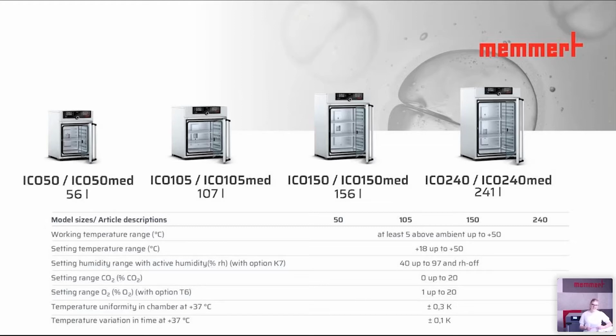With our special Memmert heating system, we were able to perfect our temperature uniformity inside the chamber at a working temperature of 37 degrees, for example, to a temperature distribution of only 0.3 Kelvin, which is quite impressive, and our temperature variation in time is even more precise at only 0.1 Kelvin. All right, now that we've had an overview of our different ICO models, we're going to have a look at those beauties in more detail again.